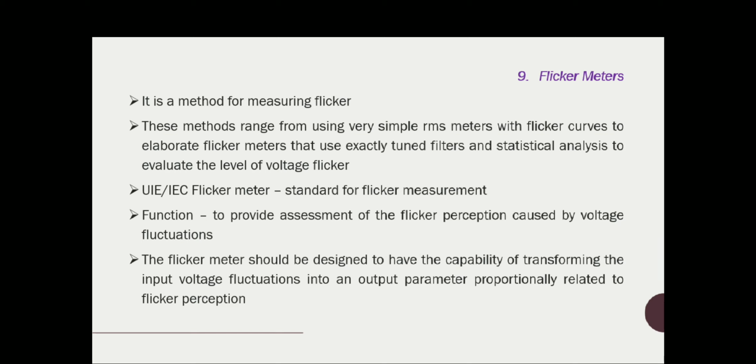So generally these meters can be divided into three sections. In the first section, the input waveform is demodulated, thus removing the carrier signal. As a result of the presence of the demodulator, a DC offset and higher frequency terms are produced. The second section removes the unwanted terms using filters, thus leaving only the modulating signal, or the flicker signal, remaining.